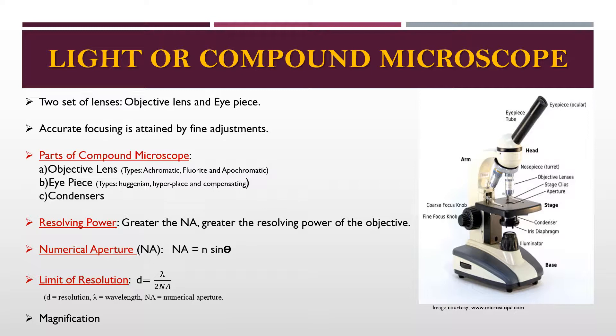Objective lenses gather light rays coming from any point on the object and unite the light at a point to further magnify the image. There are three types of objective lenses: achromatic, which is the simplest and adequate for most purposes; fluorites, in which aberrations are largely eliminated; and apochromatic, which is corrected with respect to aberrations. Aberration refers to the failure of rays to converge at one focus due to a defect in a lens or mirror.